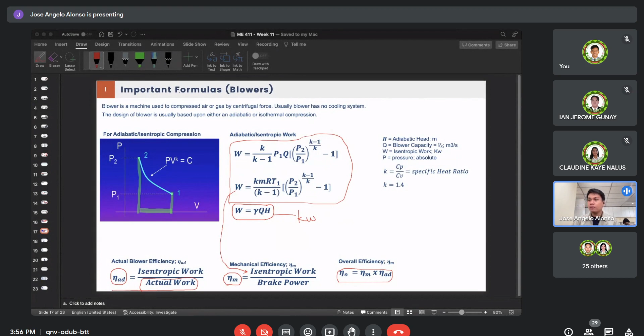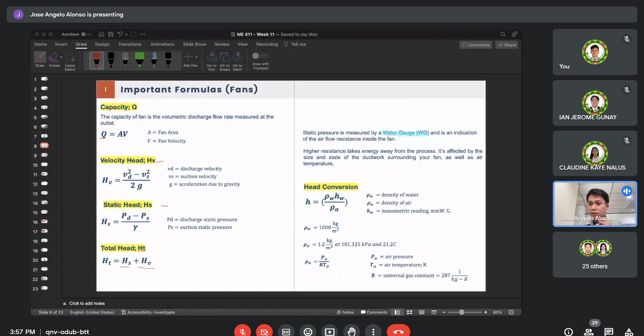So let's use this for the following problems. Hopefully we can appreciate our discussion on blowers through this example. For example 3.0, we won't use adiabatic or isentropic work here. Instead, we'll use our earlier discussions on determining total head, velocity head, and static head, using the specific weight, volume flow rate, and total head to determine the blower power. Let's correlate the equations we've given — these are important formulas related to our blower example, since the process is similar. Compression occurred in the blower, which is why we introduced adiabatic work.